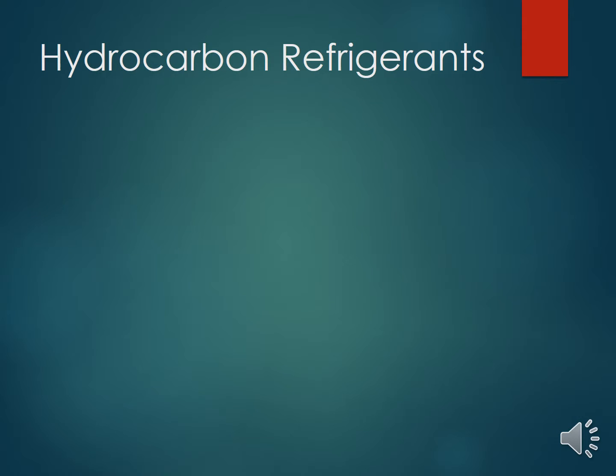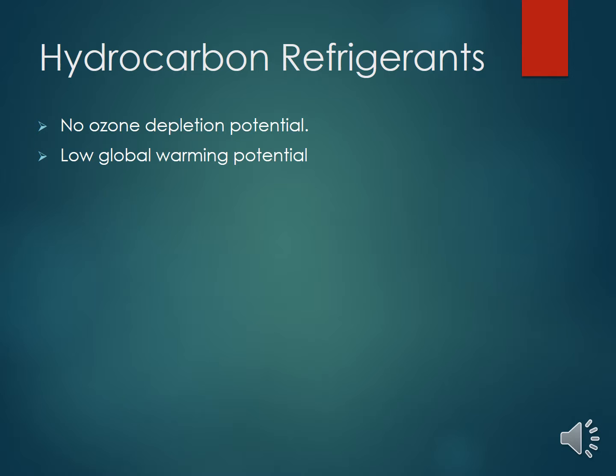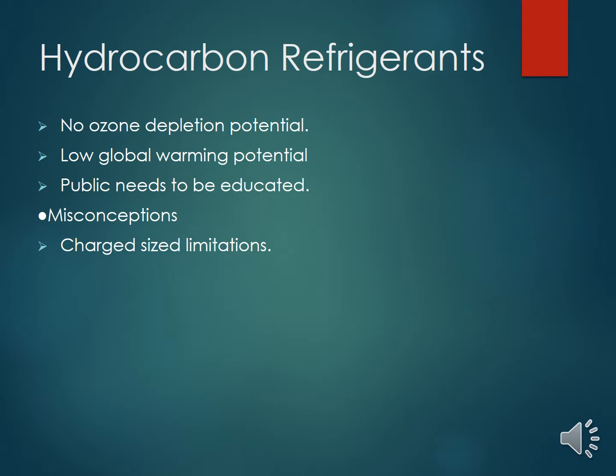As mentioned before, the prime reason to use hydrocarbon refrigerants is the fact that they have low ozone depletion potential and low global warming potential. Unfortunately, the public needs to be educated. The public has many misconceptions about hydrocarbon refrigerants. One is the size of the charge that is used in appliances that are currently out there, such as the ice chest and the refrigerators. ASHRAE currently has limitations on that to limit their explosive capability.